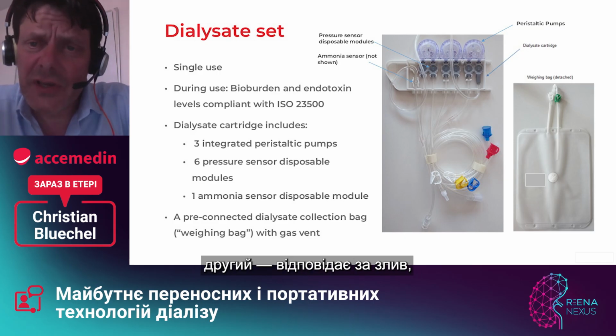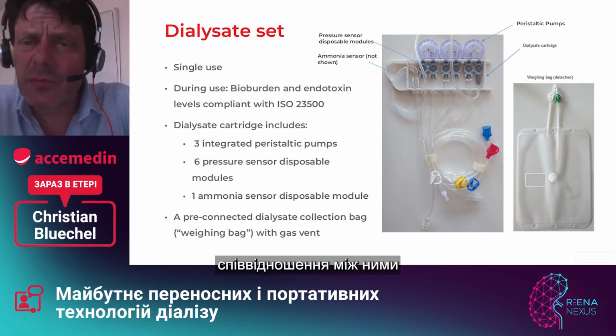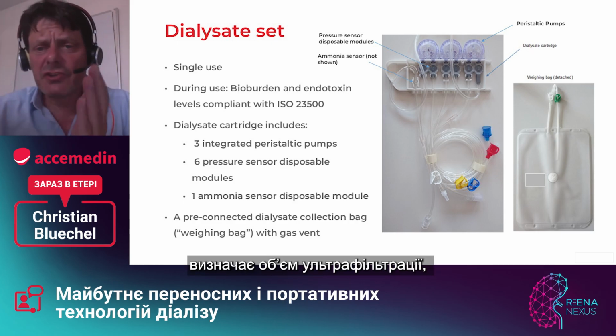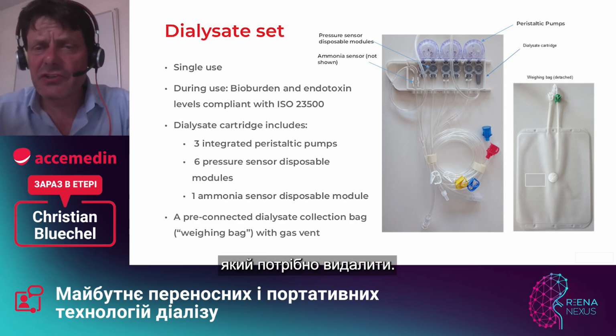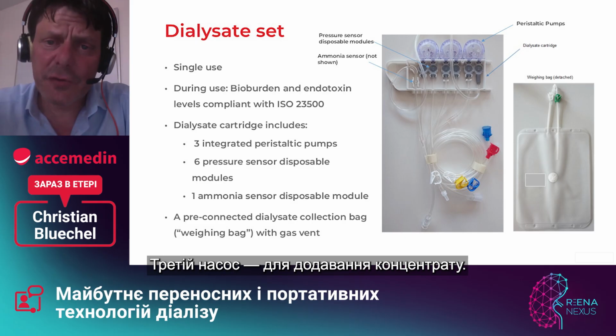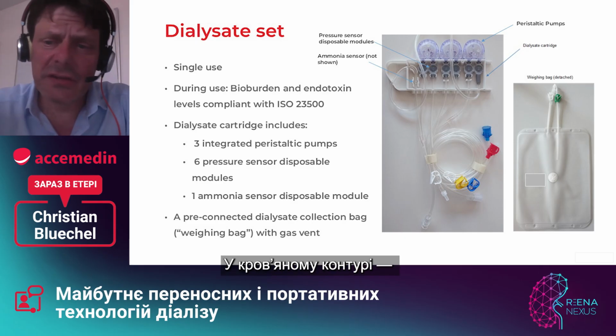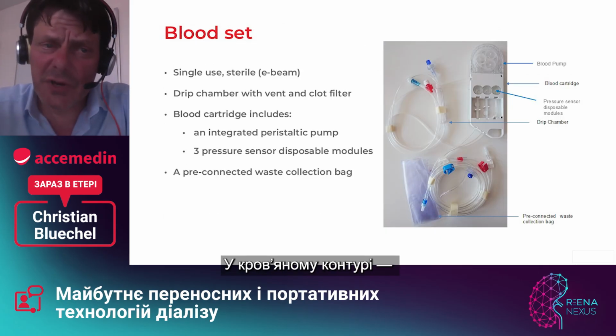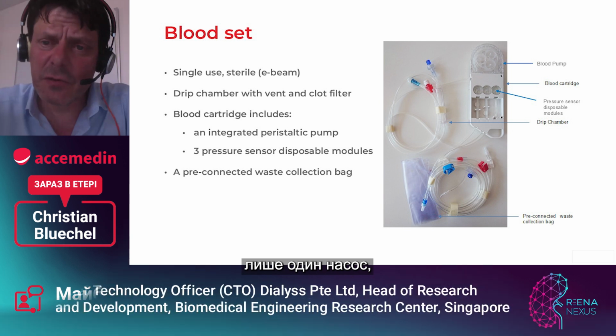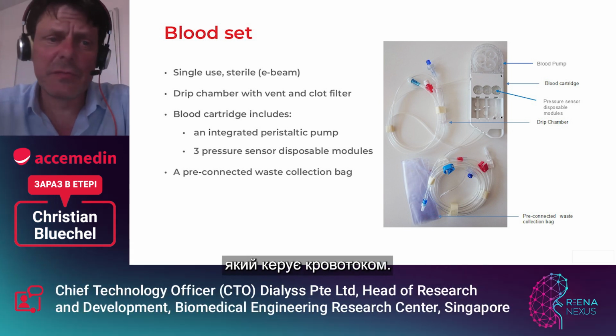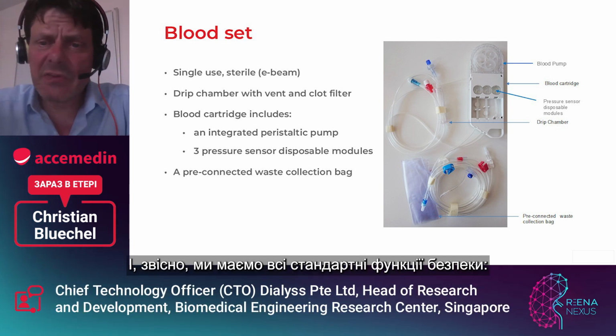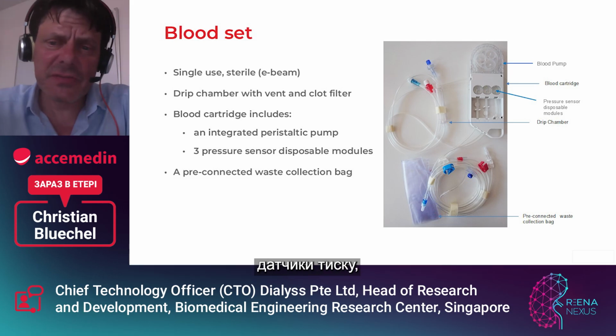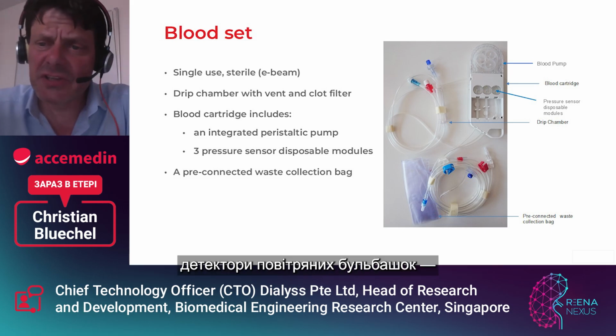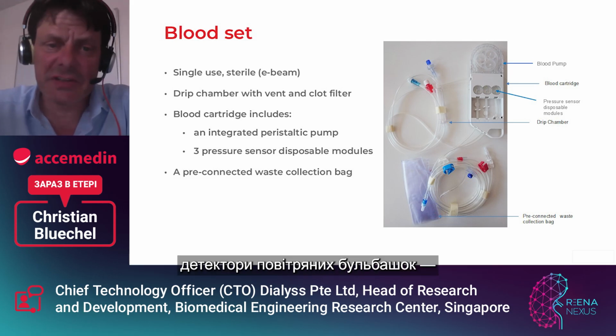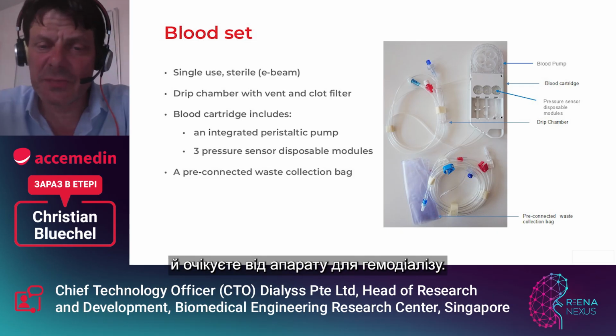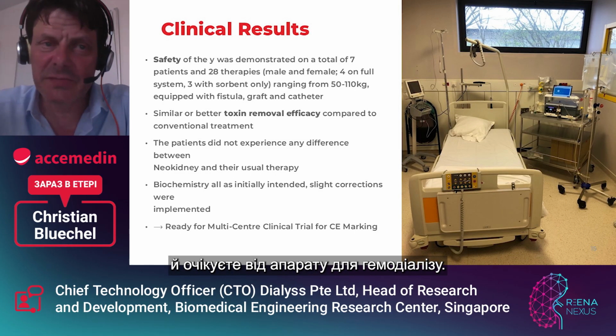We have 3 pumps: 1 pump going into the dialyzer, 1 pump coming out. The ratio of the 2 determines how much ultrafiltration is being removed. And then there's a 3rd pump for our additive solution. And on the blood cassette side, there's only 1 pump which drives the blood flow. Then we have all the normal safety features. We have the pressure sensors, the bubble detectors. It's all like what you would see and expect from a normal hemodialysis machine.